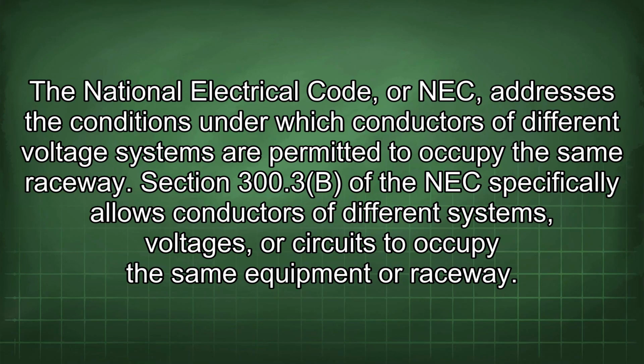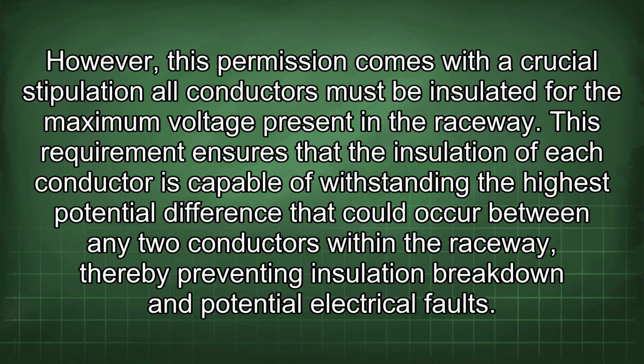The National Electrical Code, or NEC, addresses the conditions under which conductors of different voltage systems are permitted to occupy the same raceway. Section 300.3(B) of the NEC specifically allows conductors of different systems, voltages, or circuits to occupy the same equipment or raceway. However, this permission comes with a crucial stipulation: all conductors must be insulated for the maximum voltage present in the raceway. This requirement ensures that the insulation of each conductor is capable of withstanding the highest potential difference that could occur between any two conductors within the raceway, thereby preventing insulation breakdown and potential electrical faults.